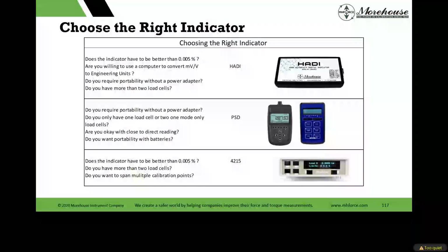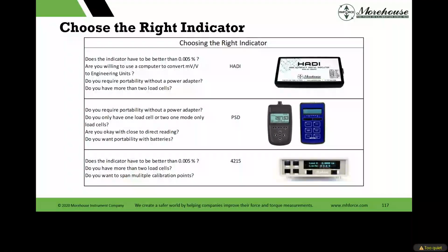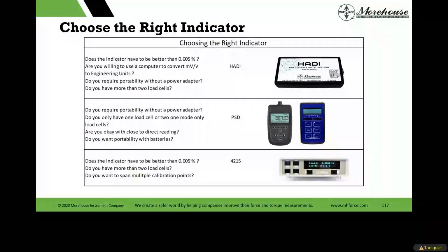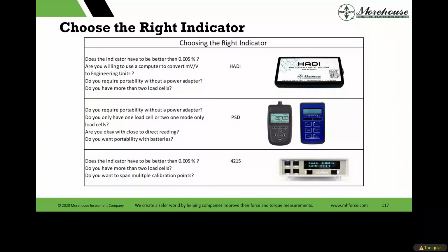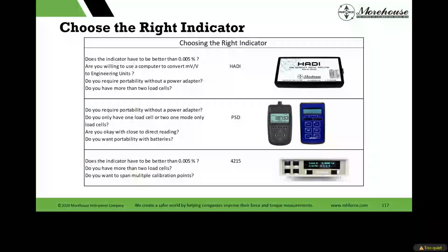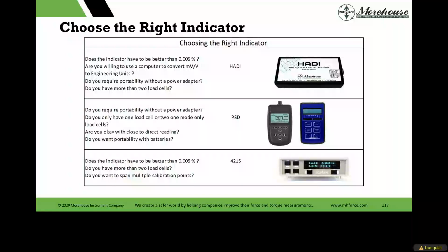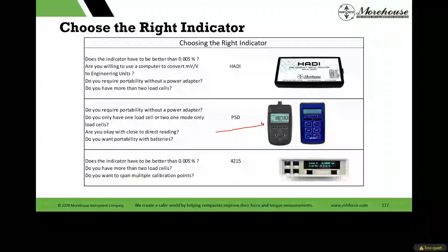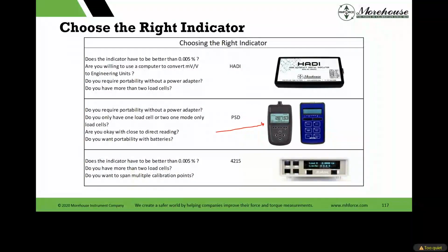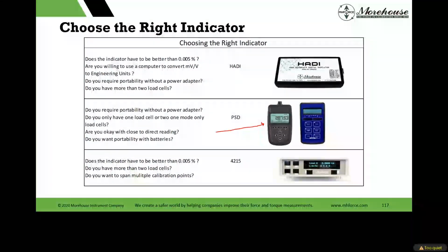Do you want portability? If I'm doing testing machines, because not everybody's doing E74, so about 31% of the people here are probably in that market where this portability, I can use coefficients, which we'll talk about. If I use a computer, now I can capture the readings by hitting spacebar or something else, dump them into a sheet, automate as much as I can the calibration of a testing machine. That might be appealing. If you just want something that's going to check a press, maybe I could get one of these handheld units that someone can program close to direct reading. There's stuff about TEDS. This PSD meter will read TEDS chips, which I'll talk about. It uses batteries, so you don't have to have a plug-in source. I can just pull the load cell out, check something really quick, and go. The price you're going to pay is more bias, less accuracy, but it depends what you're calibrating and what you have to do.